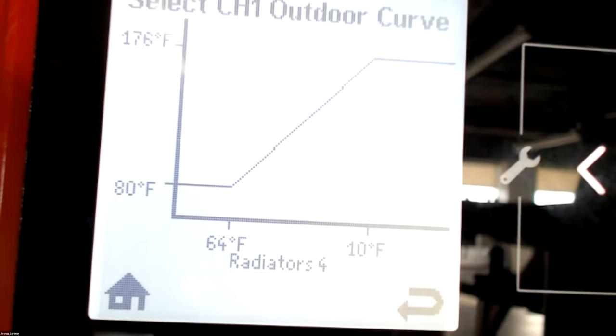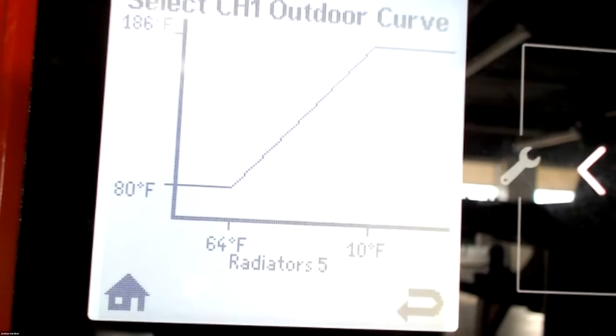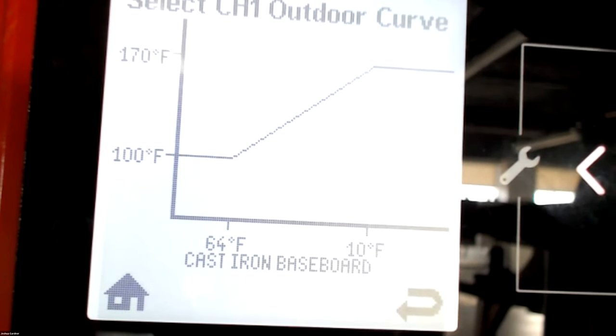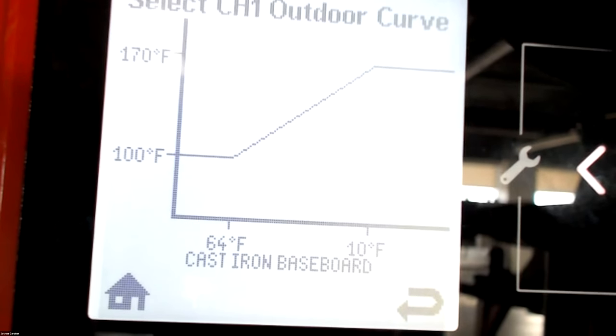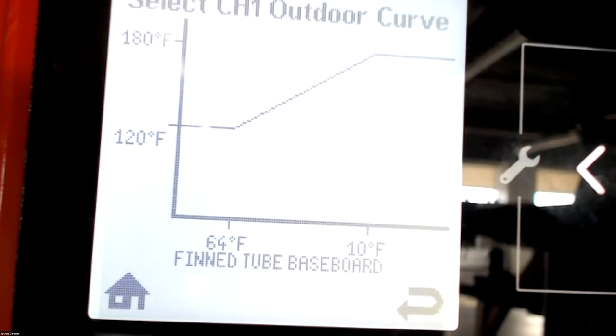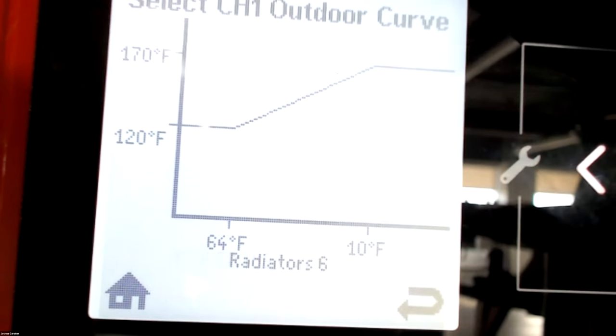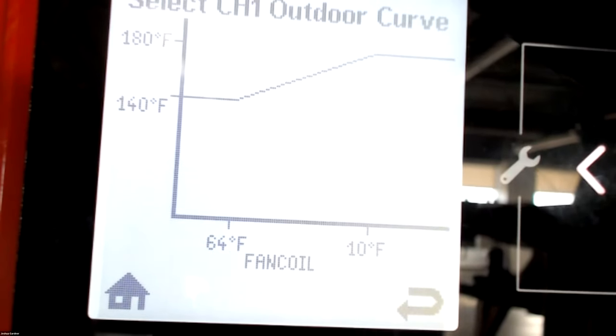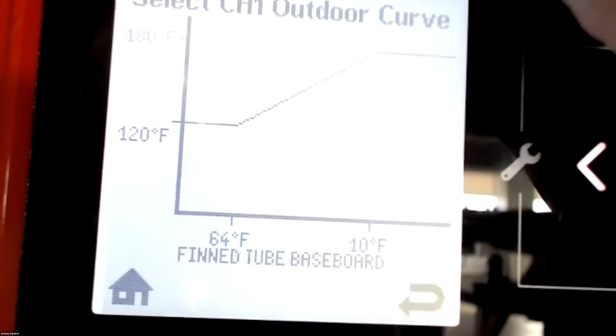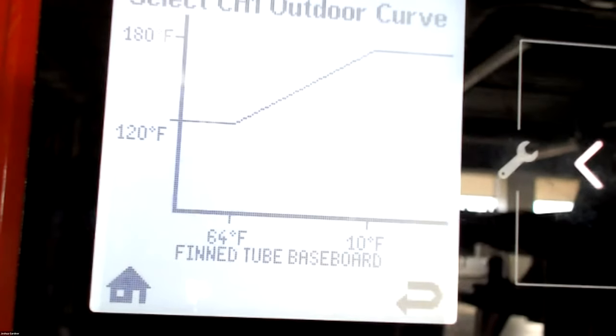That's a huge curve right there. That's a big curve. Radiators 4, 176 to 80. Then we get into cast iron baseboard. Our low temp comes up to 100. Fin tube baseboard 120 to 180. And then radiators and fan coil. But I'm going to go back to this one. Fin tube baseboard. Got a lot of guys that set this. Most installs that we have is fin tube baseboard. Probably the majority of the installs that we see.